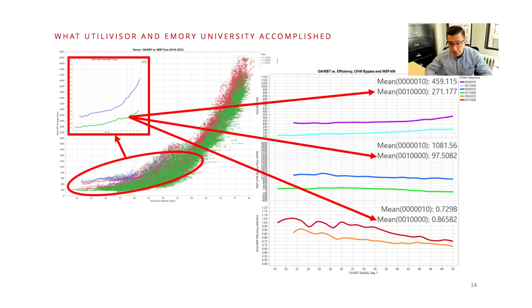The green is when the plant implemented the recommendations, started running the smaller chillers, and started operating with lower differential pressures. And if you scroll to the bottom right here, you can see the efficiency was actually a little worse. It was a little higher at 0.8, but I'm consuming a lot less power, and the plant saved an enormous amount of money implementing this ECM.